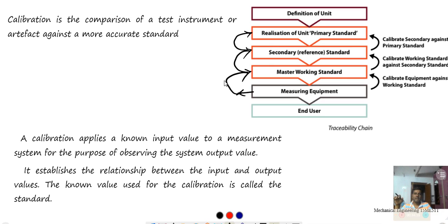Calibration is a comparison of a test instrument or artifact against a more accurate standard. That means the primary standard is more accurate compared to the secondary standard. The secondary standard is more accurate compared to the working standard. And the master working standard, that is lab equipment, is more accurate than the shop floor equipment. So a calibration applies a known input value to a measurement system for the purpose of observing the system output value.